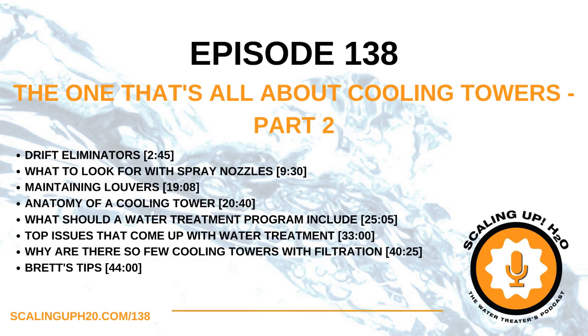Now, when you say split stream, what do you mean by that? You're softening the water, but then you're blending it back in with some of the raw city water or well water. So, maybe you have 200 ppm of hardness coming in on the city, and you're going to blend that back in with your softened water. So you're doing a 50-50 split. So that's just more of a controls thing. So that's great in theory, but it takes a well set up softener system to be able to do that correctly.